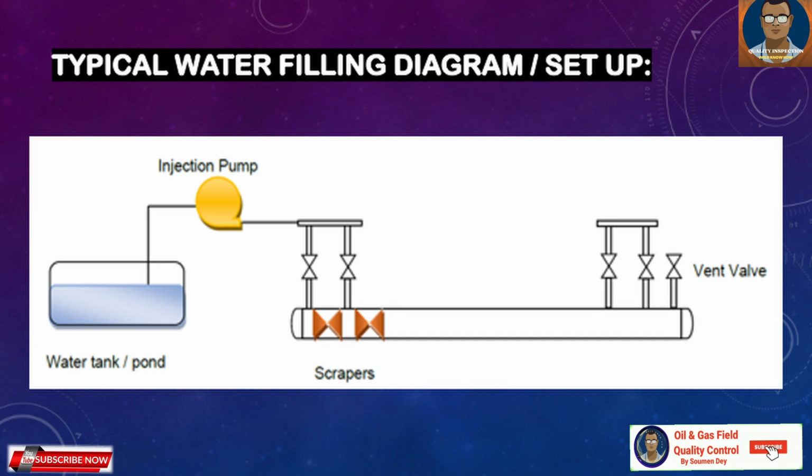On the way, we are injecting oxygen scavenger and biocides into the system where the filling is ongoing at a specific rate. Let's say, for example, we need to fill 10,000 liters of water. We need to arrange 2.3 liters of ammonium bisulfite and a dosing pump, and we will inject this 2.3 liters at a uniform rate throughout the filling procedure. We will decide the flow rate by calculating that 10,000 liters takes 10 hours. So within 10 hours this 2.3 liters should enter the system. Based on the time, we need to calculate the flow of the dosing pump.